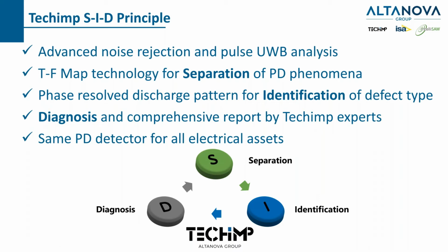And the reason I say that is just because you have partial discharge doesn't mean you have a problem. It depends on the asset. Different levels of PD will affect assets differently. And what I mean by that is that, say you have 8 millivolts of partial discharge in a cable insulation. Well, that could be very, very dangerous to a cable. But 8 millivolts in a transformer or switchgear is meaningless. It's not a danger. So we have to identify the asset that partial discharge is in before we can diagnose if there's a problem yet.